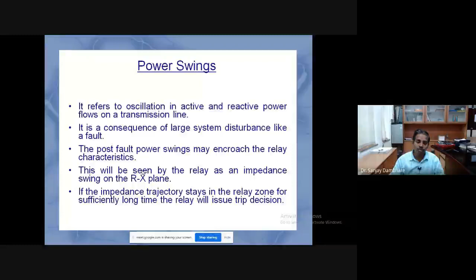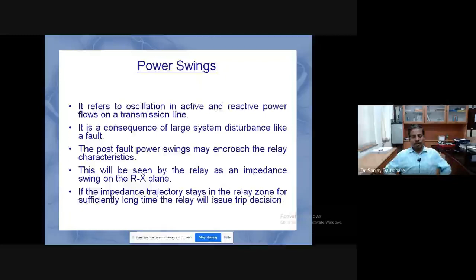And the point is that all this power swing will be seen by the relay as an impedance swing on the RX plane, and if that impedance goes below the set value for some time, then the distance relay may trip, and that is how the power swing affects the distance relay operation very badly. So if the impedance trajectory stays in the relay zone for a sufficiently long time, then the relay will issue the trip decision. So this is the operating point.